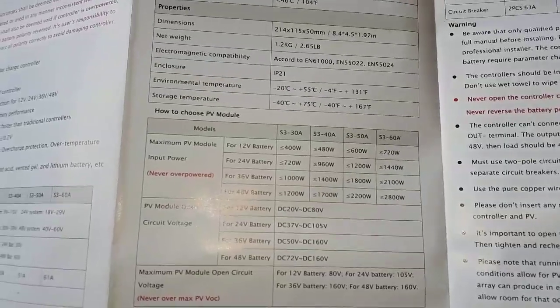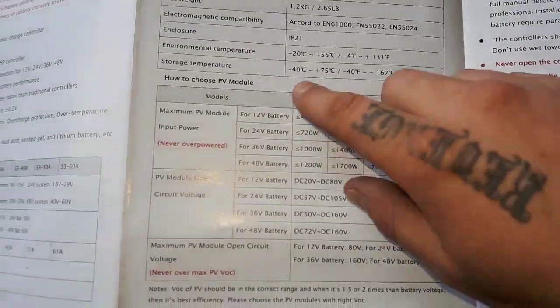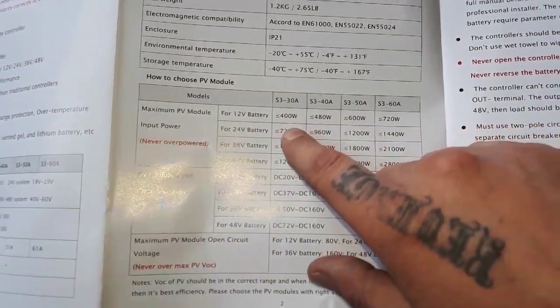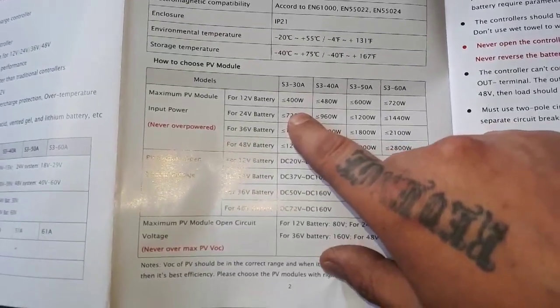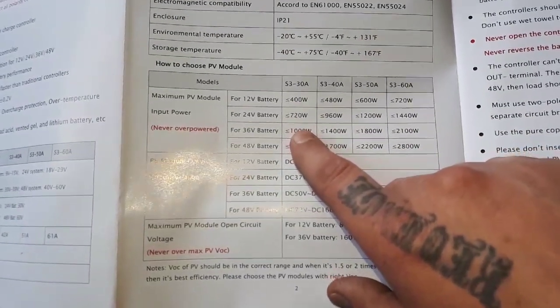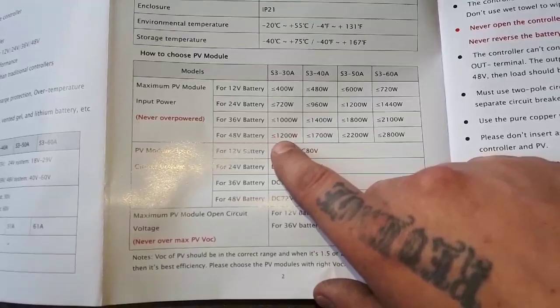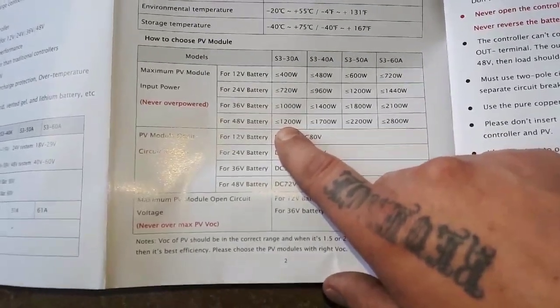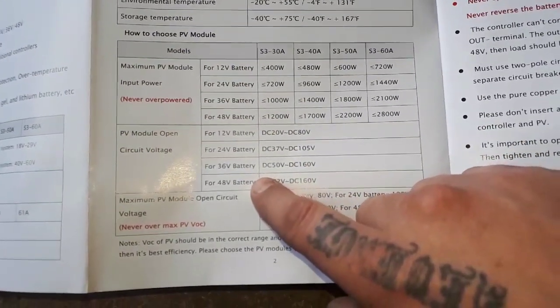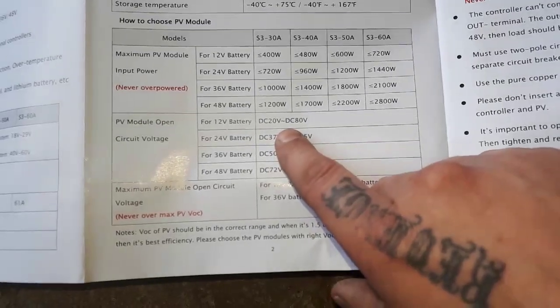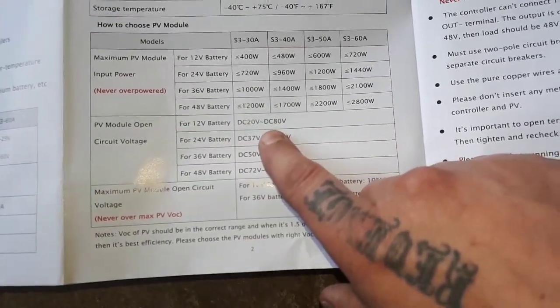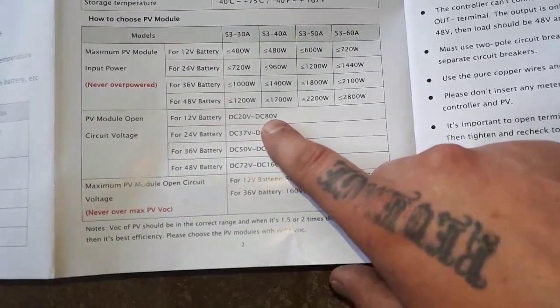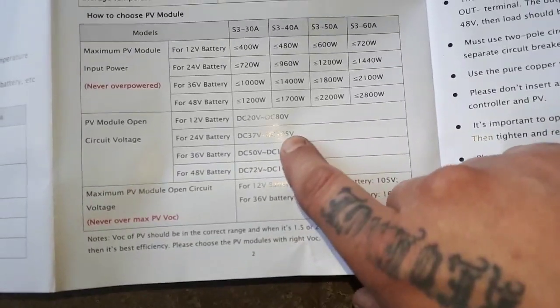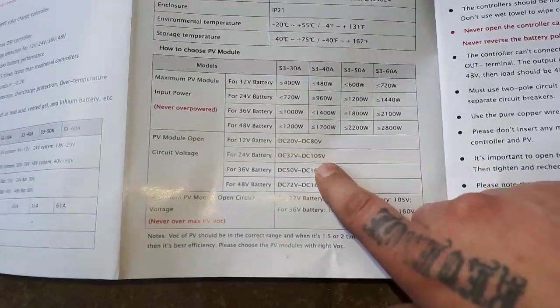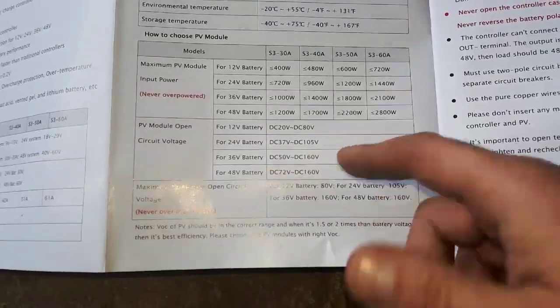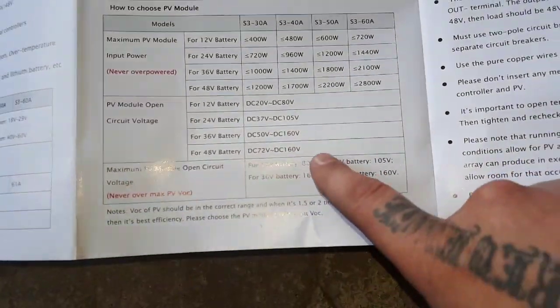Dimensions, PV, I got the 30, so I can go 400 watts with a 12 volt, 720, 1000, and 1200. These are your open voltages. So a 12 volt system, you can't go past 80, and for 24 volt, you can't go past 105. And you see how it is, 48 volt is 160.